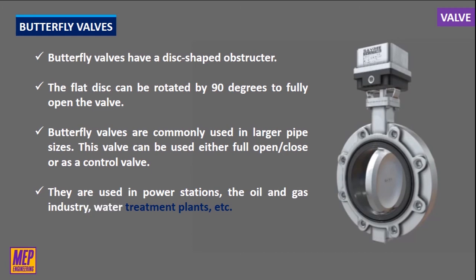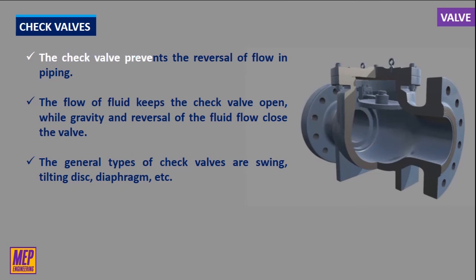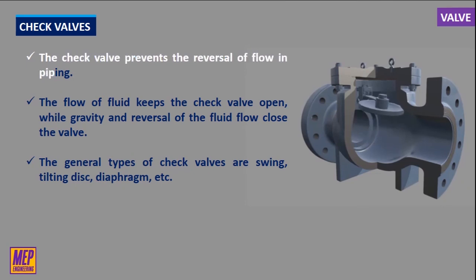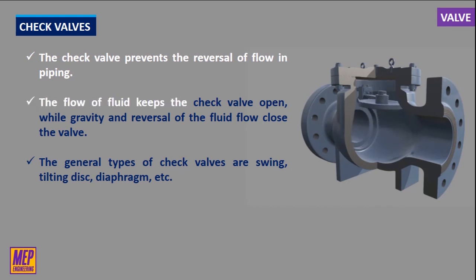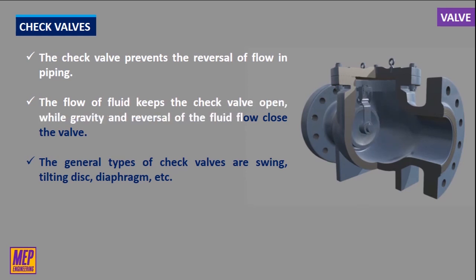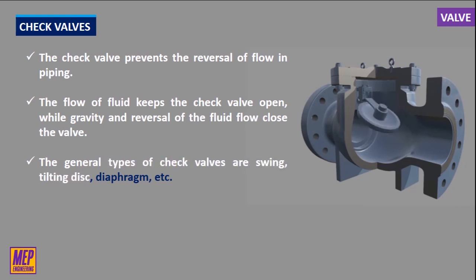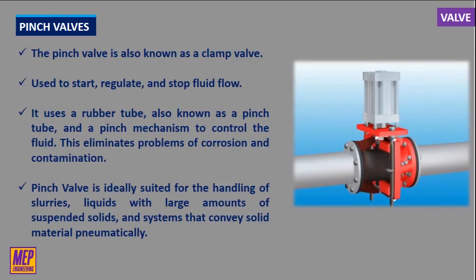Butterfly valves can be used either fully open, fully closed, or as a control valve. They are used in power stations, the oil and gas industry, water treatment plants, etc. Check valves prevent the reversal of flow in piping. These valves are activated by the flowing material in the pipeline. The flow of fluid keeps the check valve open, while gravity and reversal of fluid flow close the valve. General types of check valves include swing, tilting disk, and diaphragm types.